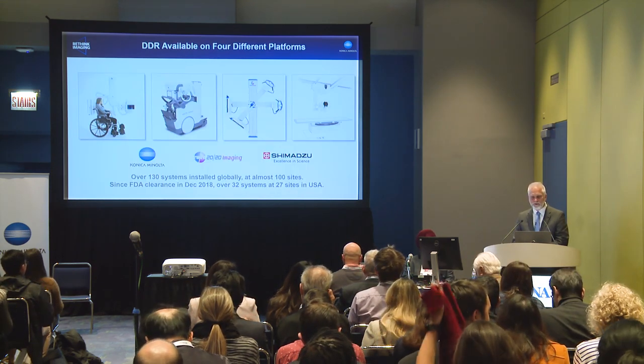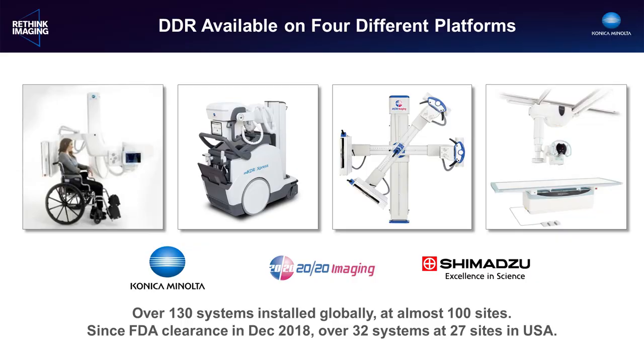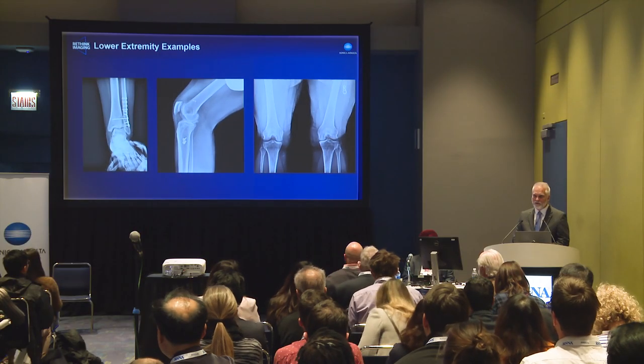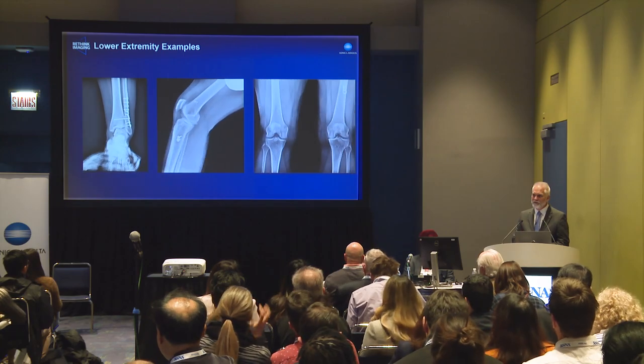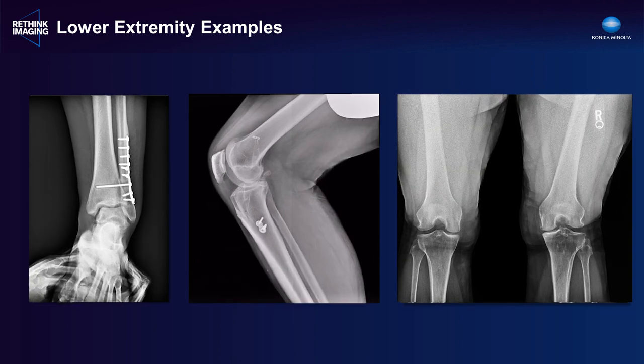DDR is currently available on four different acquisition platforms from three different vendors. In addition to the conventional overhead room, it's available on floor-mounted straight and U-arms. It has recently been cleared by the FDA for use with a wireless detector on a mobile setup so you can image the patient at the bedside. With this variety of systems, you can image the patient wherever normal x-rays would be taken, duplicating any of your standard x-ray views and exams.